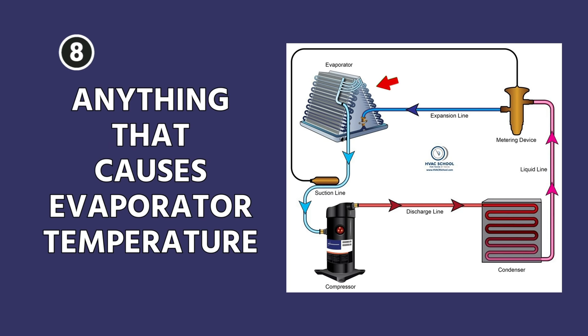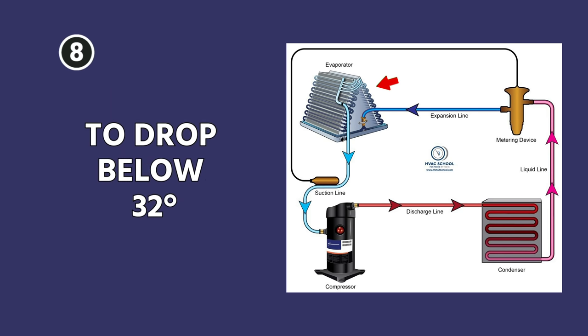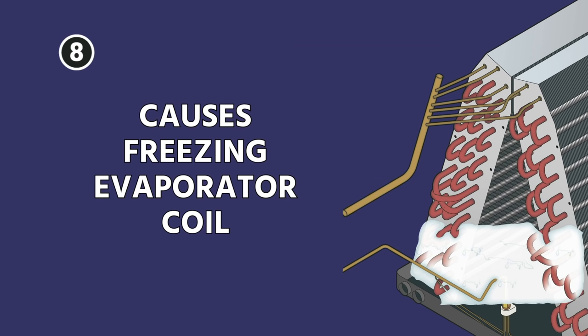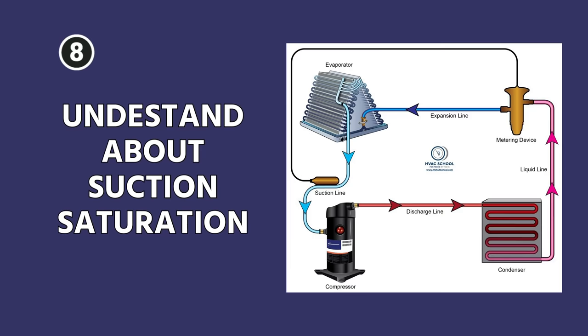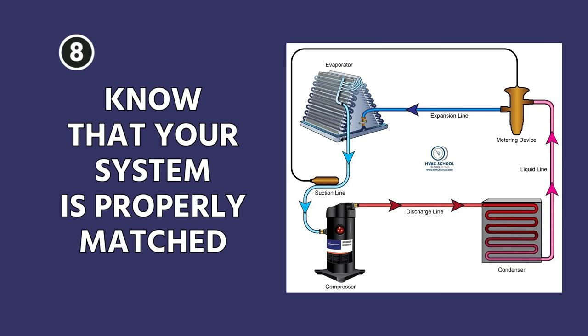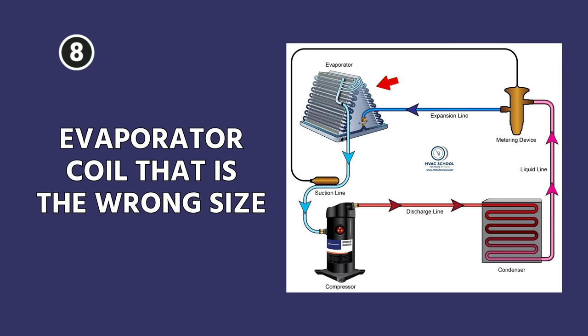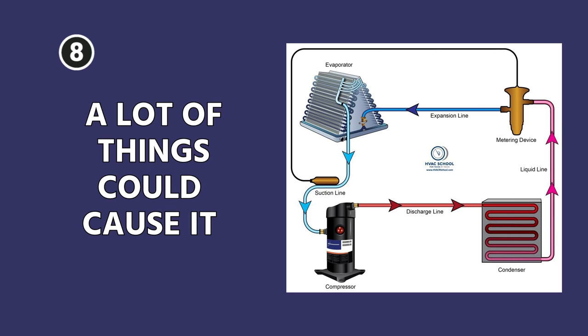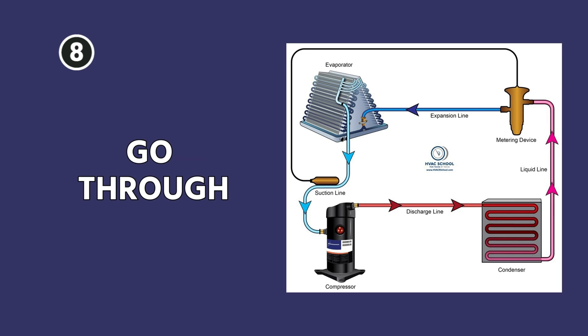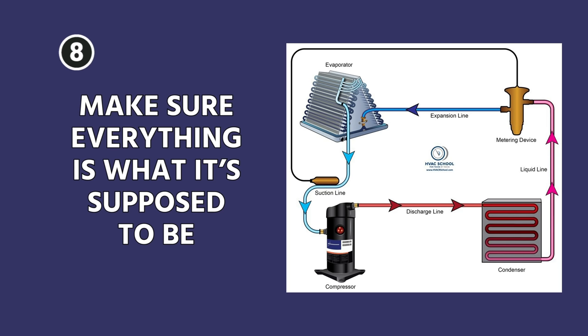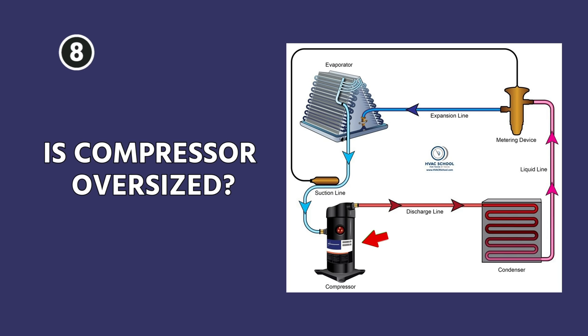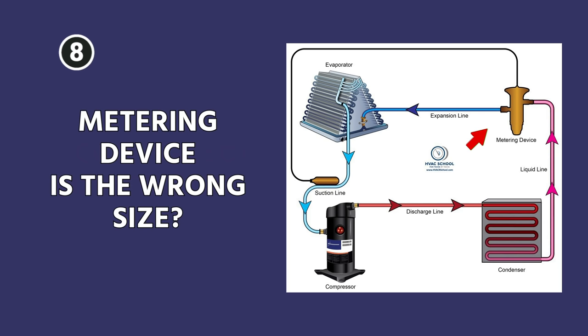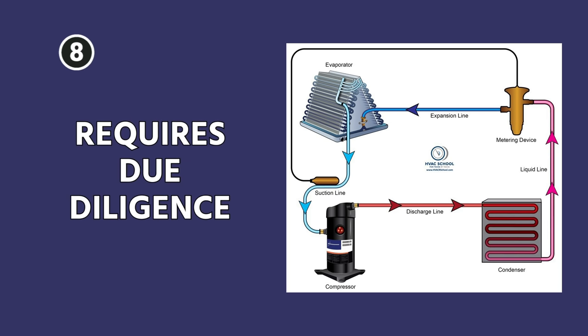You want to confirm all refrigeration cycle components and processes are functioning properly, as there are a lot of things that can potentially go wrong depending on the type of system you're working on. Anything that causes your evaporator temperature to drop below 32 degrees is what causes a freezing evaporator coil. You have to understand suction saturation and know that your system is properly matched. If you have an evaporator coil that's the wrong size to match the condensing unit, that can cause the problem. Make sure nobody slammed in a compressor that's way oversized or a metering device that's the wrong size.